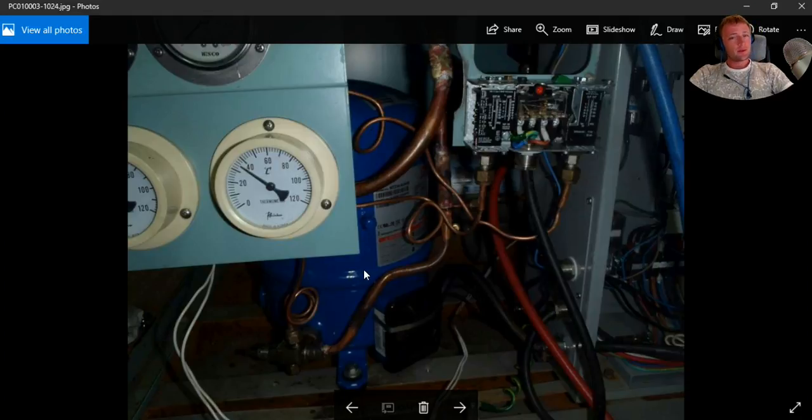But the main problem was the valves. To burn the compressor motor is a little bit difficult. You will burn it if your protection is not working, but in that case it was working. We ordered a new compressor, which comes ready like this, with feet here, with support.